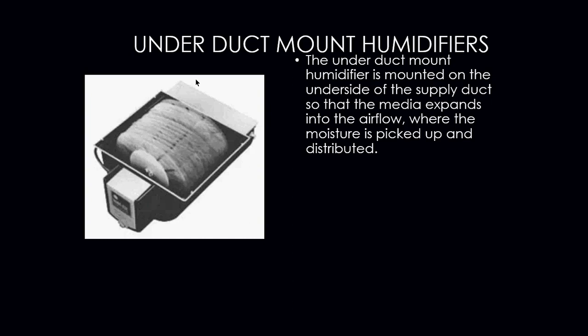Okay, these do have some disadvantages, obviously, because this entire basin where this media is sitting is going to be filled up with water. And as long as that water is in there, we are going to have buildup, and it's going to get dirty. Okay, with that dirtiness, we're going to have algae, and we can actually have issues with the humidifier over time. It could slug up, it can become massively dirty, especially if we do not have preventative maintenance on them. So humidifiers need to be maintained on a yearly basis, if not maybe even a monthly basis, depending on how much they're being used.